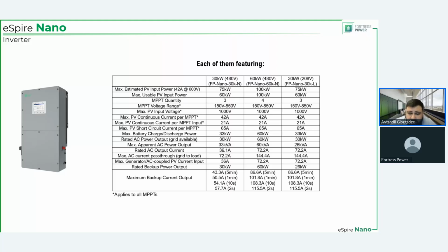So the 30 kilowatt inverters, yes, they are both called 30 kilowatts, but the 208 volt inverter can only output 26 kVA, and the 480 volt 30 kilowatt inverter can output 30 kilowatts, right? That all comes down to current and how the power is calculated based on current, because you'll notice that AC output current is different between them. Rated AC output current for the 480 volt inverter is 36, and for the 208 volt it is 72. So in those terms, the 60 kilowatt and the 30 kilowatt 208 volt inverters are much more similar in terms of current than the 60 kilowatt 480 volt inverter and the 30 kilowatt 480 volt inverter.